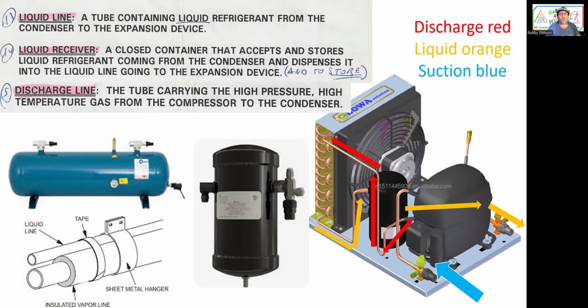Why? Because during summer, we have more heat in the air. It takes more to reject the heat from the condenser. Alrighty. So therefore, the liquid receiver is empty in the summer, and all the Freon is in the condenser. But in winter, it's the other way around. We have less heat in the air. We don't need to reject that much heat. The liquid receiver is full of Freon, and the condenser doesn't have that much Freon in it. So the liquid receiver's job is for winter and summer, depending on the temperature outside. If temperature is very, very hot, the liquid receiver is going to be empty, Freon in the condenser. If the temperature is very cold outside, then Freon will go in the receiver. Okay, it's not needed on cap tube systems.